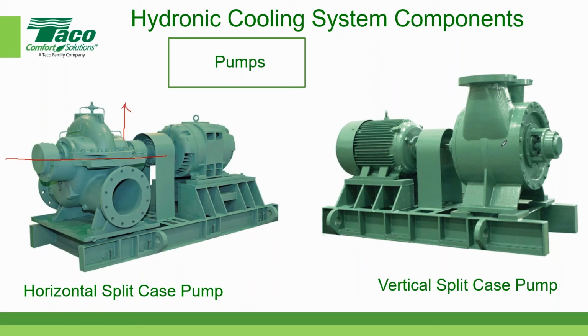And a vertical split case, as the name implies, you can barely see it. You can certainly see it in the back. There's that seam right there, and that seam is along a vertical line, kind of like that. And so that's where the name comes from. On the vertical split case, which is also true of the horizontal split case, the suction side, this is the suction side here on this pump, and there's the discharge in the background. The suction is always one pipe size larger than the discharge. That's also true of most of the horizontal split case.